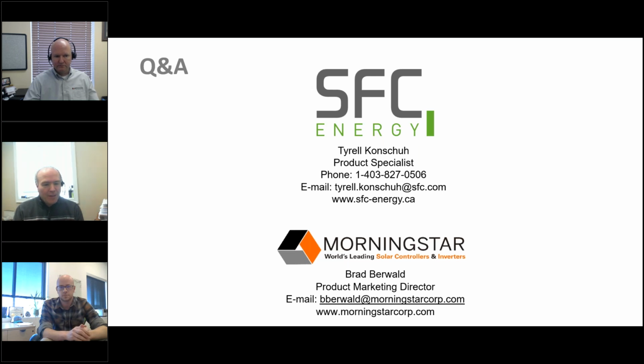A follow-up question: what is the life cycle of the fuel cell and what needs to be replaced? Using the Pro 2800, the 125 watt unit, as an example, we guarantee the unit for 6,000 hours, and typically we try to size your system to use 500 to 1,000 hours a year as a target. Some systems based on solar availability will accumulate more hours, and some based on low load may accumulate fewer. We try to give you a long runtime and lifespan out of your system. After that, if the power has derated enough that it can no longer support and replace the load, you'll want to look at either refurbishing or replacing your fuel cell.